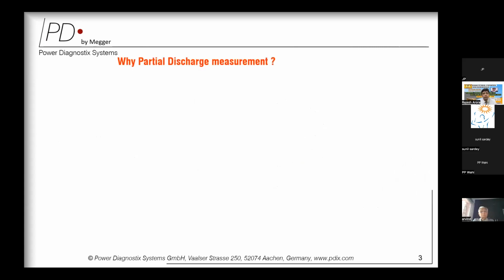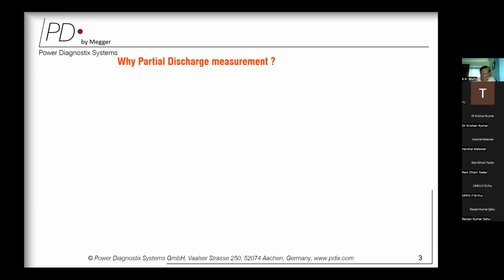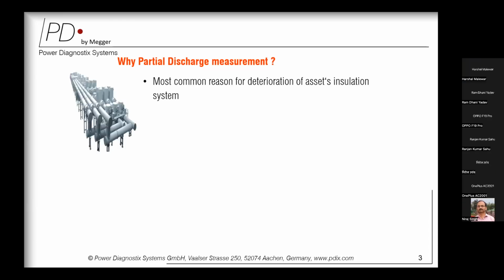So let's first understand when we start with the topic partial discharge. Why partial discharge measurement? Because we have been doing several measurements in GIS, like monitoring the gas density, checking the gas quality, or doing the breaker timing measurement, breaker contact resistance measurement. Why do we need to do a partial discharge measurement? Why is there a need to do this particular measurement? If we understand a little bit why it is required, it is the most common reason.